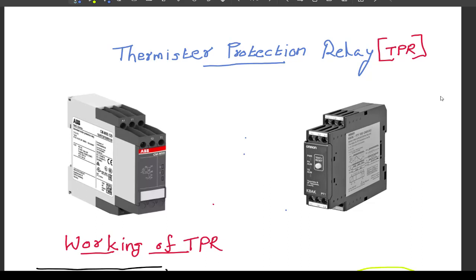Anyway, we are going for this thermistor protection relay. The overcurrent relay or thermal overload relay can only protect the motor in case it is drawing more current. But if the winding temperature is too high due to single phase operation or insufficient cooling, there will be no arrangement for tripping the motor or cutting out the supply to the motor so that it can save the winding insulation. For that purpose, we use the thermistor protection relay.